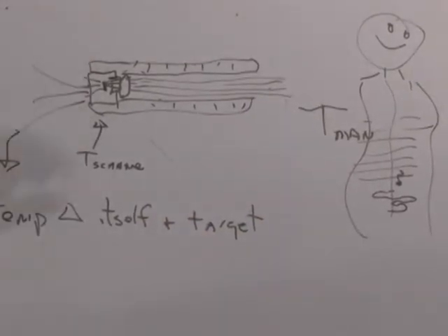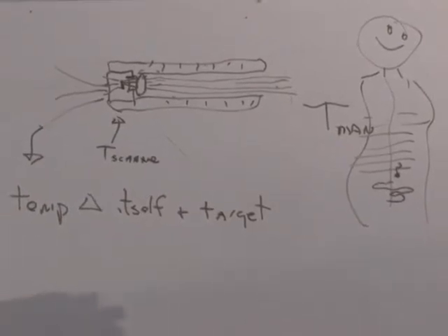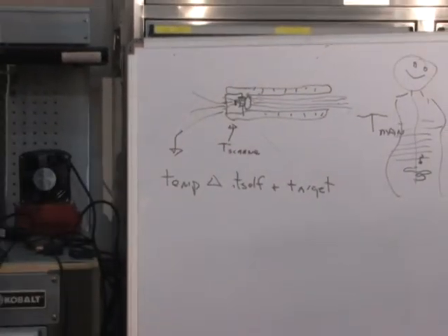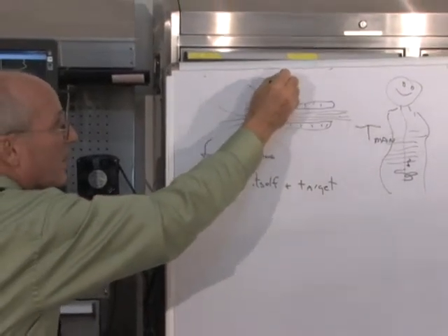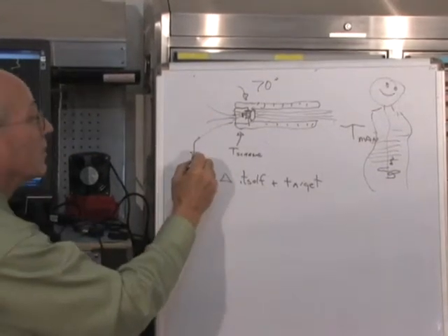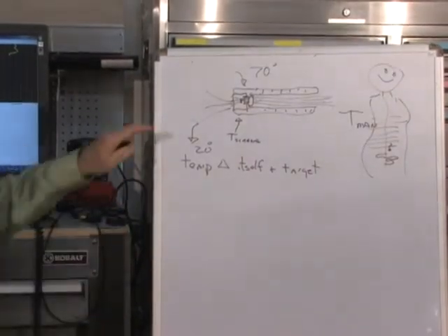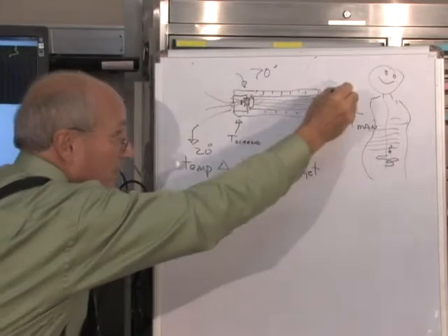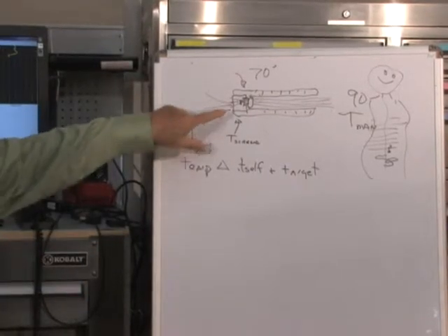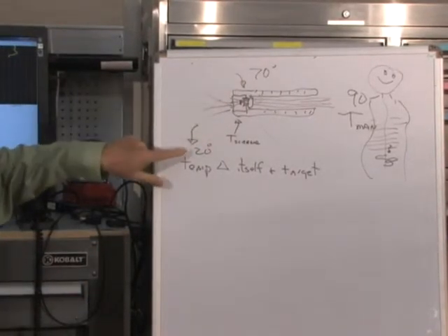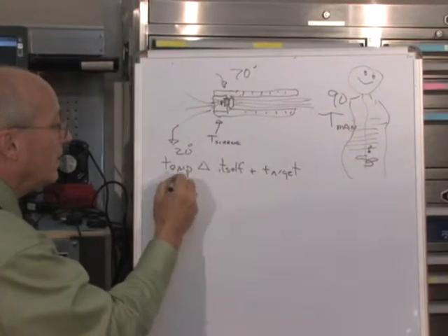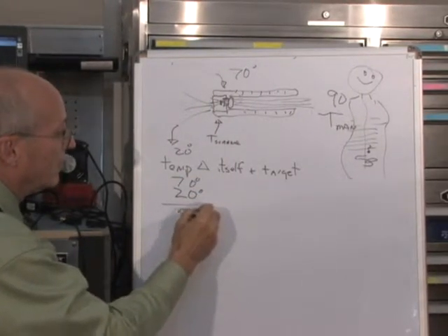Pretty simple. If the temperature of the scanner head in your office is, let's say, 70 degrees, and the temperature output from the sensor is 20 degrees, we know that the target that we're looking at is 90 degrees. If we know the temperature of the scanner head and we have the output from the infrared sensor and we add them together, 20 and 70, we have 90 degrees.